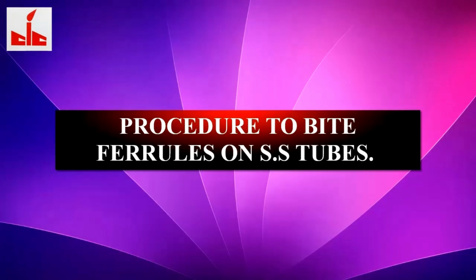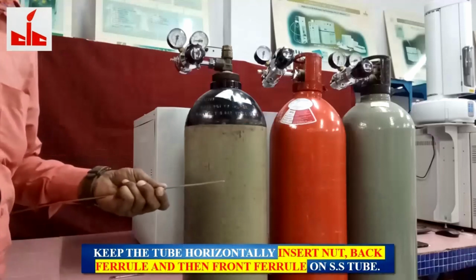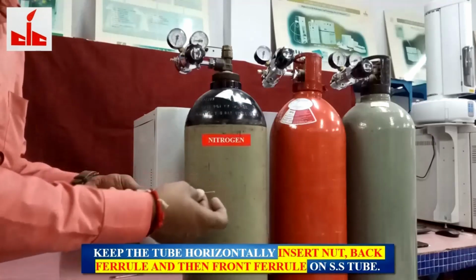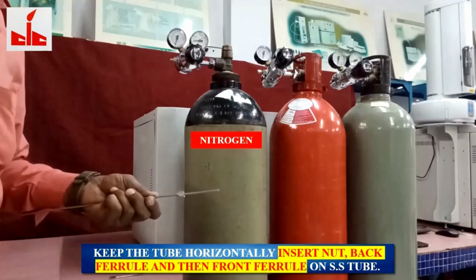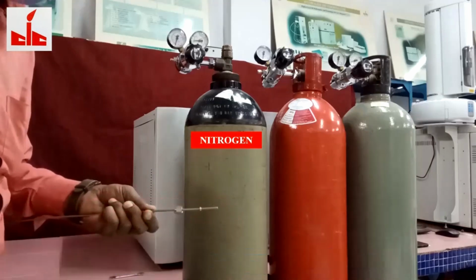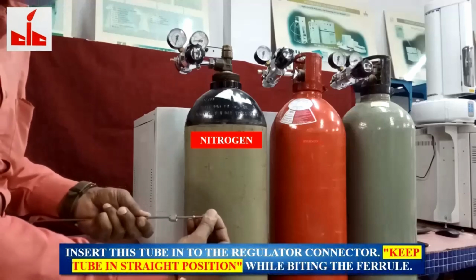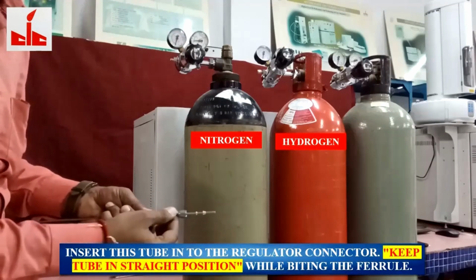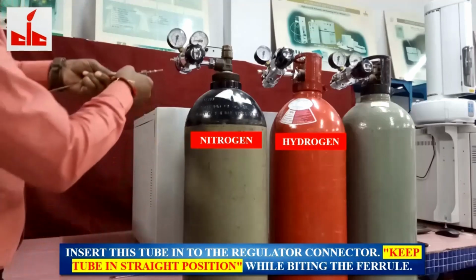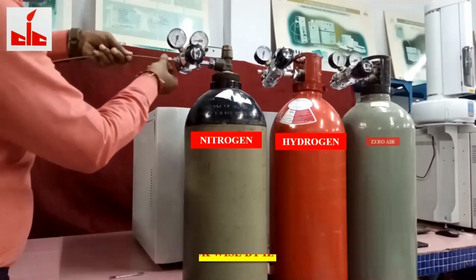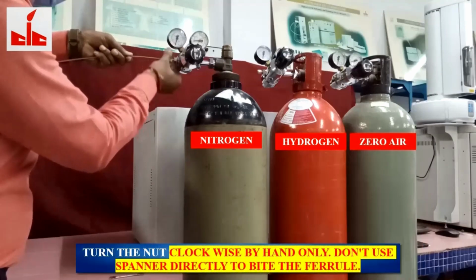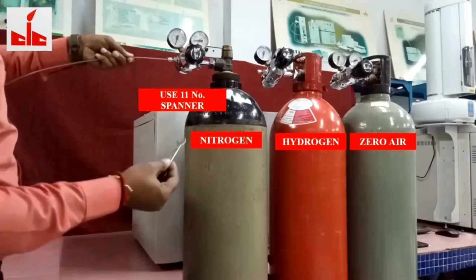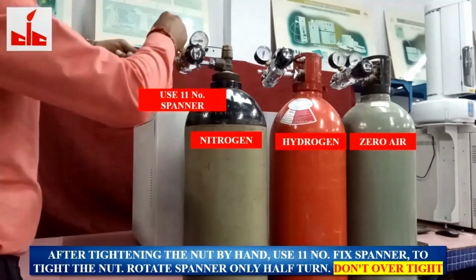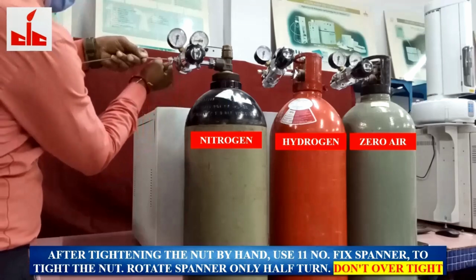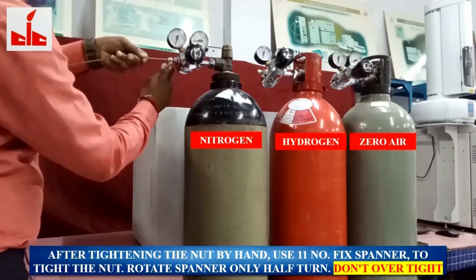Procedure to bite ferrules on SS tubes. Keep the tube horizontal, insert the nut, back ferrule, then front ferrule on the SS tube. Insert this tube into the regulator connector. Keep the tube in a straight position while biting the ferrule. Turn the nut clockwise by hand only. Don't use a spanner directly to bite the ferrule. After tightening the nut by hand, use an 11 number fixed spanner to tighten the nut. Rotate the spanner only half turn. Do not overtighten.